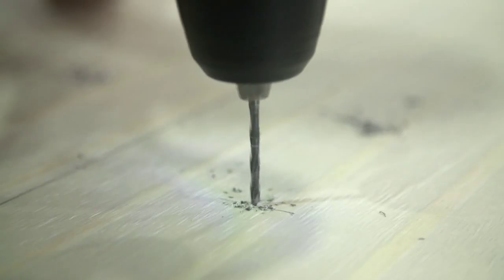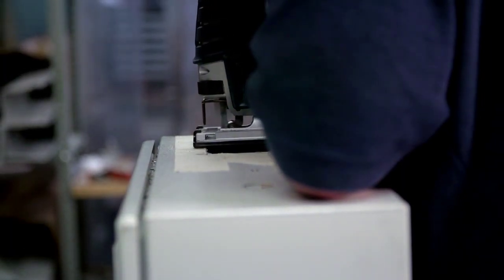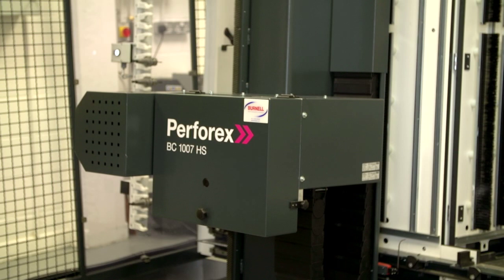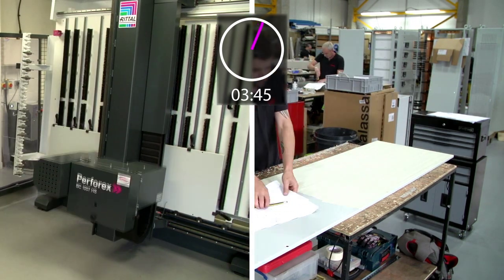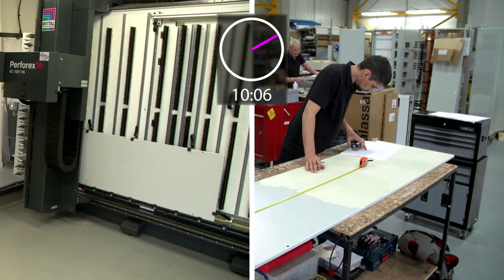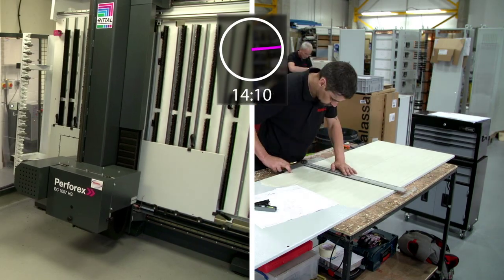It's now a case of it going through the Perforex machine cleanly, safely, with hardly any wasted materials anymore. Perforex has eliminated the risk of injury to our shop floor staff as we no longer use jigsaws, drills and punches. The Perforex machine has safety features built in which prevent the operator getting anywhere near any moving parts. Originally, without Perforex, a cutout for HMIs, pilot devices and handles using punches, drills and jigsaws would take about 8 to 10 hours. With Perforex and ePlan that time is dialled down to 15 minutes, which frees up more production time for other jobs.